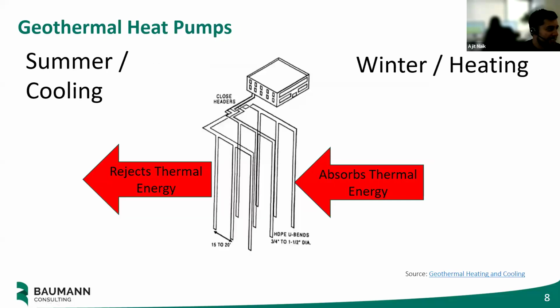So this led to the idea of how else could we provide that heating and cooling instead of a boiler and a cooling tower. That's the idea of a geothermal heat pump. So the key point is, in the wintertime, when all of our heat pumps are kicking out cold water because they're blowing warm air, we need a way to warm that water up. If it's not cool to use a boiler to warm that water up, the idea behind geothermal is to use the ground. You bury pipes in the ground where it's always pretty steady, kind of neutral temperature. It never goes down below the frost line. And in the winter, you can extract that energy right from the ground.